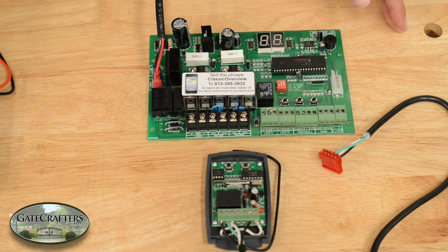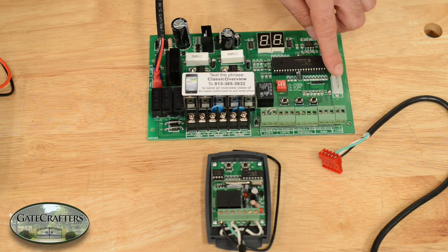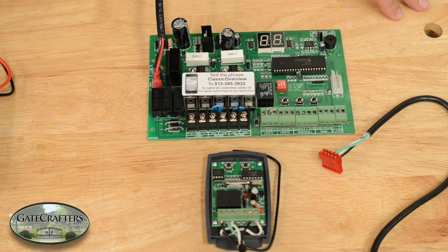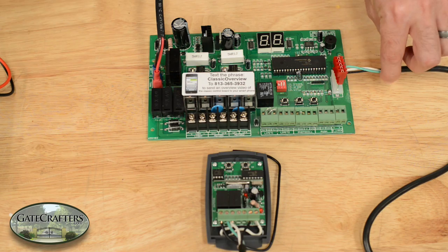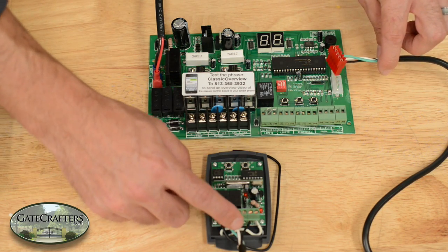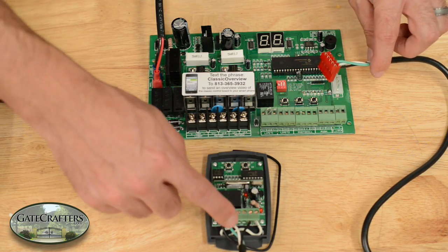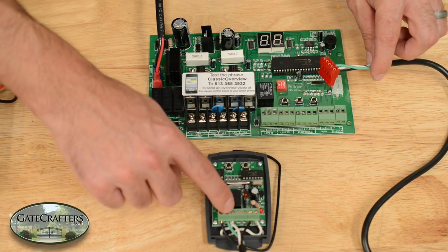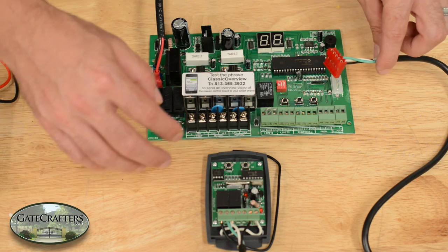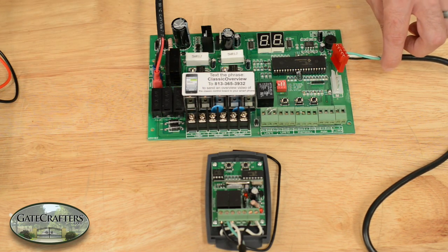One key note, if this is a new installation and this is not working during the new installation, we make every attempt to warn you: do not plug this in before connecting these wires to these terminals. Because if the wire that goes into this terminal and the wire that goes into this terminal ever touch, it will short out the board and this connection will stop working.